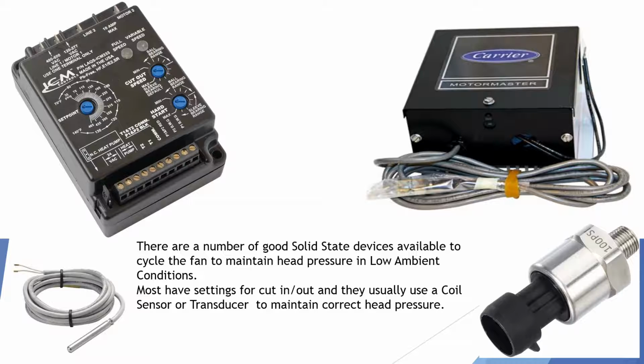There are a number of good solid-state devices available to cycle the fan to maintain head pressure in low ambient conditions. Most have settings for cut in and cut out, and they usually use a coil sensor or a transducer to maintain correct head pressure.